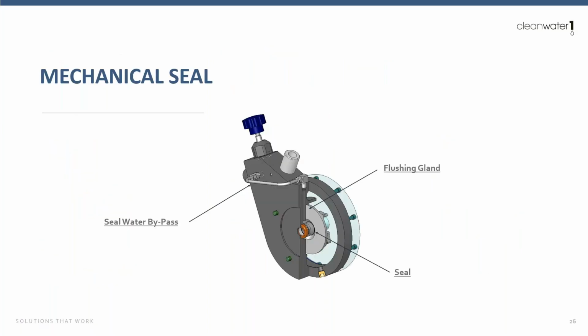When we're talking about a mechanical or a hydromechanical system, one of the maintenance points here is the mechanical seal, right? So this is the seal between the mixer shaft and the impeller. As good of a lubricant as emulsion polymer is when it's wet, it can really become a glue when it's dry. And what can happen is if you're operating a system and then you shut down for an extended period of time and that polymer dries on that mechanical seal, once you start the system back up, it could potentially crack that seal.